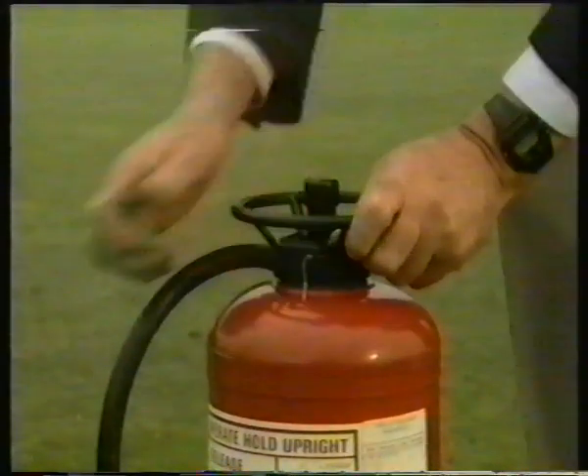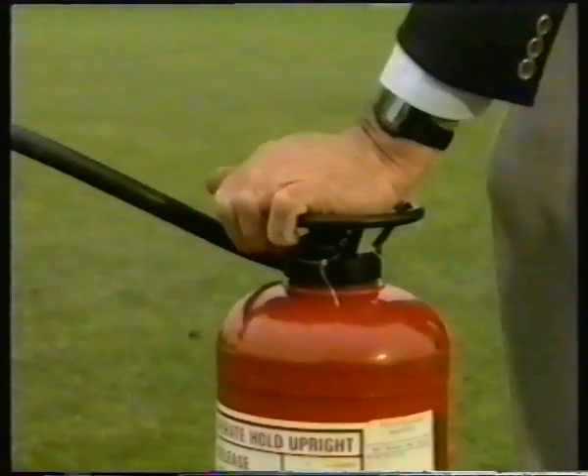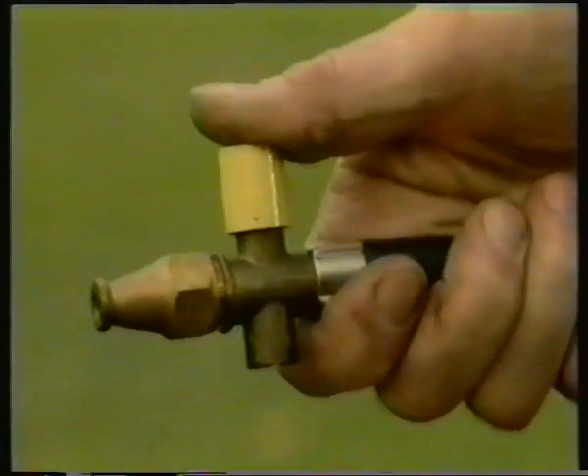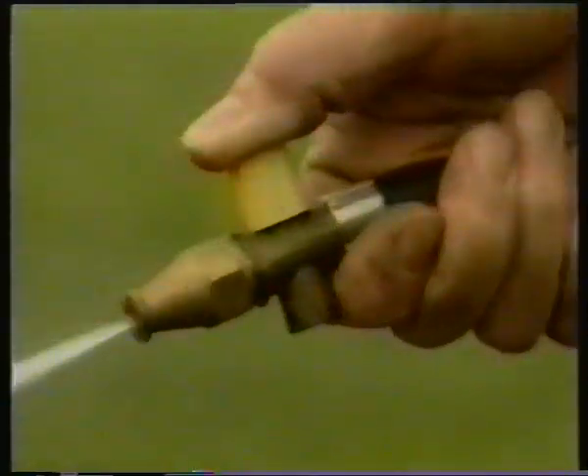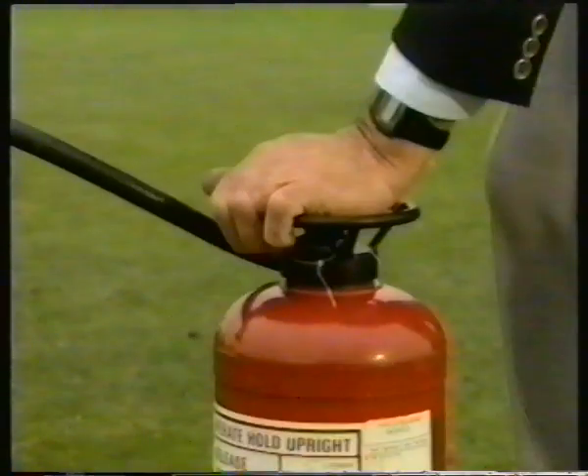This extinguisher is operated by pushing the safety stirrup to one side, sharply striking the plunger to break an internal seal, and then pressing the valve by the nozzle to discharge and control the jet of water. Should there not be a nozzle valve, the jet will start as soon as the plunger is struck and will continue until all the water is used up.